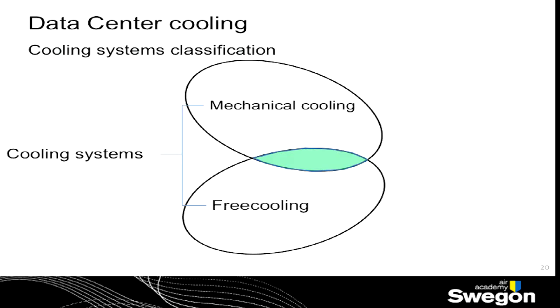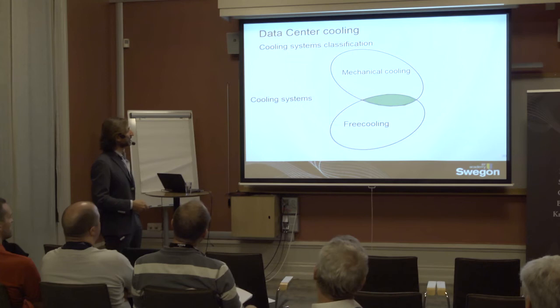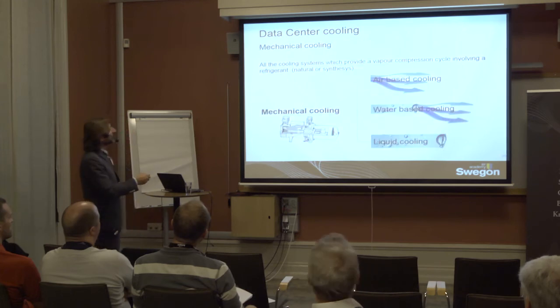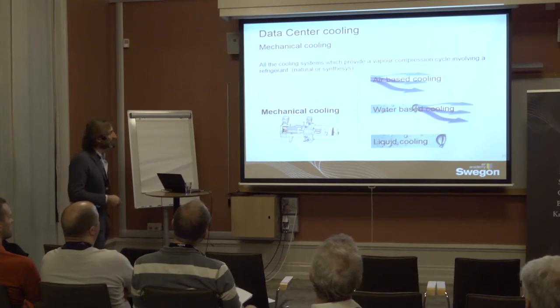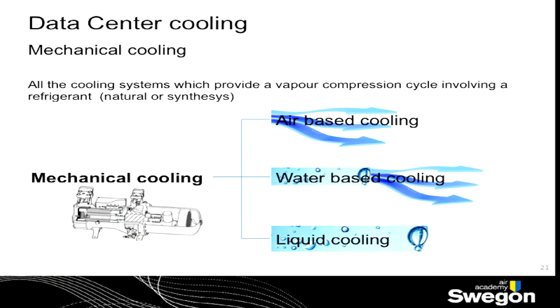most important topic, the cooling system in data centers. I think in a rough way we can divide it into two main systems, the mechanical cooling and the free cooling. They have an intersection. They are not completely detached. The mechanical cooling is intended as everything which uses a vapor compression cycle. And it can be air-based cooling, water-based, or liquid cooling, depending on which is the medium that transports the cooling power into the building.